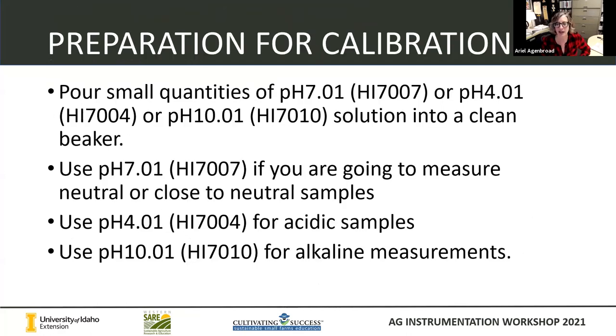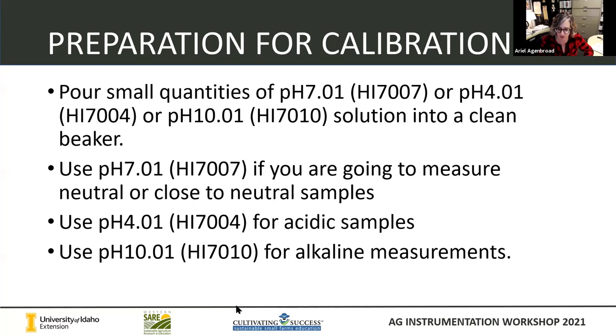So how do we calibrate our pH meters? To calibrate you need some calibration solution. Your kits are all going to come with this pH 7.01 solution, which is really good if you're going to be measuring neutral or close-to-neutral samples. If you're going to be measuring what you already know are acidic samples, you'll probably want to get some pH 4.01 solution. And typically in southern Idaho we use the 10.01 for alkaline measurements, because a lot of our soils are going to be eight and above.